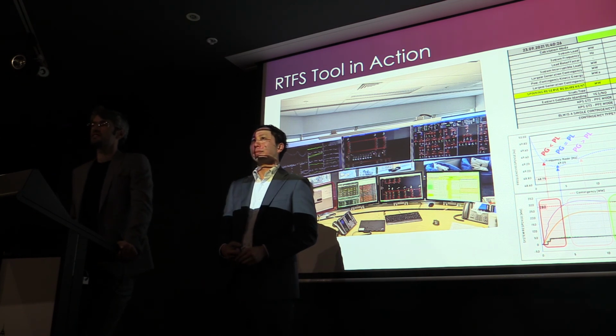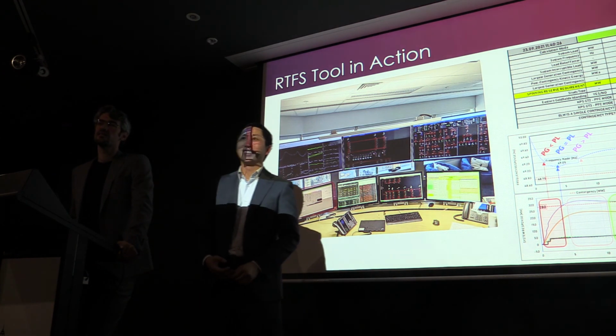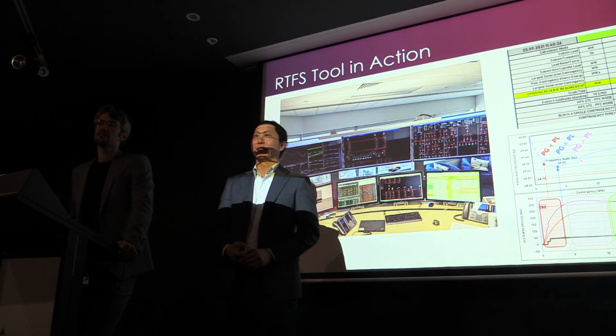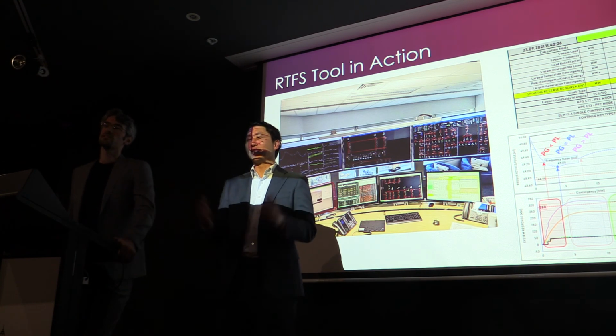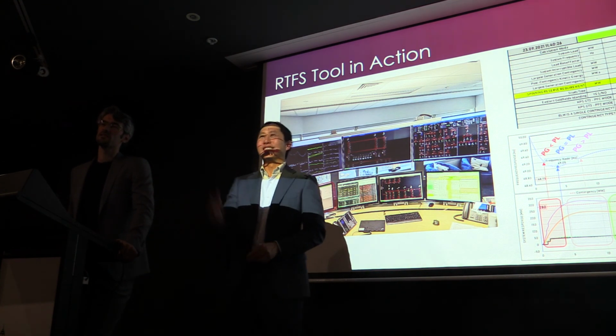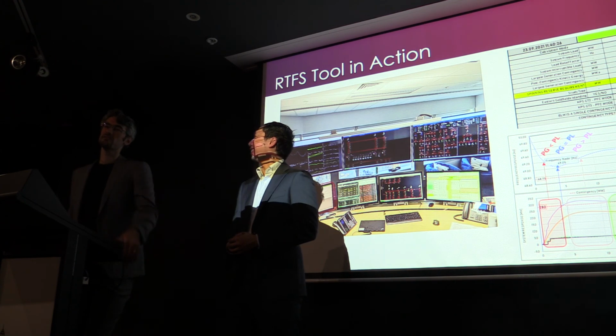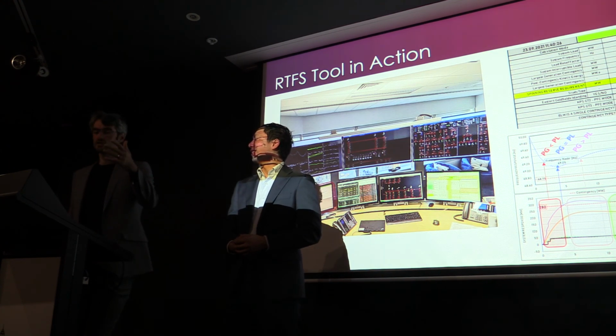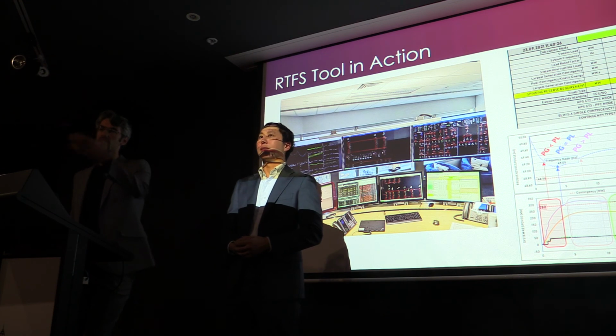So looking forward, in the case of generation, the generators are going to be more prolific and smaller, so these problems will be less, because when you lose a generator, the biggest generator in the future might be 12 to 15 megawatts. There are two things: one, the transmission issue. Two, the generation contingency is less, and if they all provide spinning reserve at the same time, the ramp rate would be higher, so that definitely helps us.